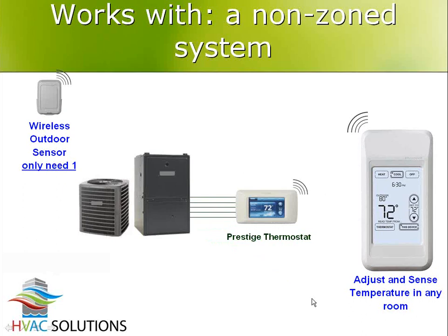If I move over to the Prestige, it works a little bit differently. With the traditional Prestige, he's talking wirelessly to the portable comfort control, he's talking wirelessly to the outdoor air temperature sensor, but he's hardwired to the furnace. Now when the new Prestige IAQ stat comes out this month, it'll be a little bit different, and you won't need the wires between the stat and the furnace. You do still need two wires to the stat, and that might come from the furnace because you need 24-volt power, but maybe you don't want to take it from the furnace because that's a long run. Maybe you want to put it on a small transformer and pull it out of the attic or wherever. So you might not have those wires at all, but it certainly won't be as many wires. It'll be two at the most with the new Prestige IAQ.